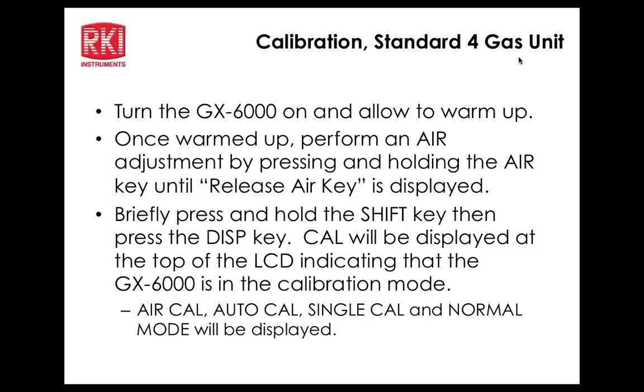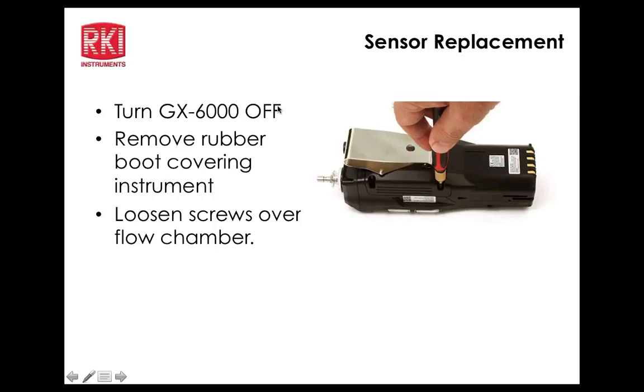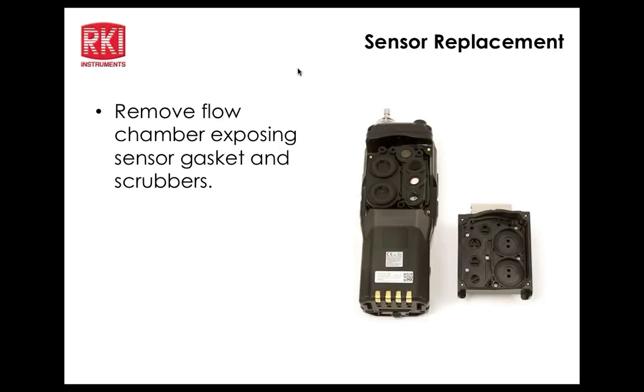All right. What we'll do now is go back to the PowerPoint because we'll pick up with some. Let me go ahead and turn the unit off right now. Okay. So going back to the slide presentation here, we remove 4 screws on the back of the upper back panel of the unit, and then that will enable you to take the back off and expose the sensor well. Lost control here. Okay. So once you get the back off, you can see the rubber gasketing assembly, and that will contain the filters. So you've got the H2S removal filter at the top over the LEL sensor, and then just below that to the right, the charcoal filter for the CO sensor.